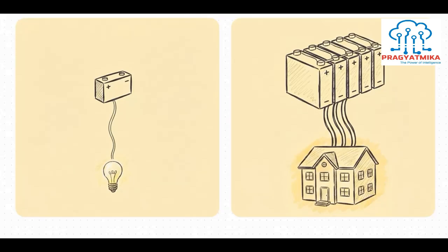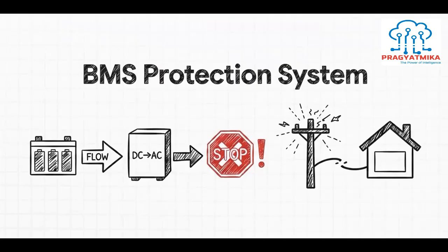Imagine your client wants to charge their EV with a level 2 charger that pulls a continuous 7 kilowatts. If you've spec'd a 0.5 C battery that only outputs 5, well, that system is going to trip immediately. If you ignore the C rate and your inverter requests more current than the battery's limit, the battery management system steps in. It will immediately throttle the output, or worse, shut the whole system down completely. Cue those dreaded customer callbacks. The inverter and the battery have to constantly communicate. If the inverter demands more than the BMS decides is safe, the BMS just opens the contactors to protect the cells, and the lights go out.